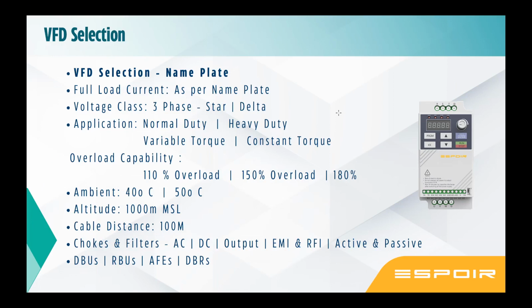So, for example, take a downhill conveyor where the loading happens at the top and the unloading happens at the bottom. Now you don't have to apply any energy because the moment you start, the material in the conveyor is simply going to come down. This time, the input power to the motor is lesser than the output regen energy. It means the motor is simply going to work as a generator. Now, how are you going to use this energy? You just connect an RBU and divert this energy to the grid. So wherever motoring is needed in the motor, it will draw the energy from this grid. It's a very complex design and engineering solution, which needs a lot of selection and engineering as per the application, the site condition and the time duration, how much it is going to regen. So this is a very big subject to work on. We can always discuss this.